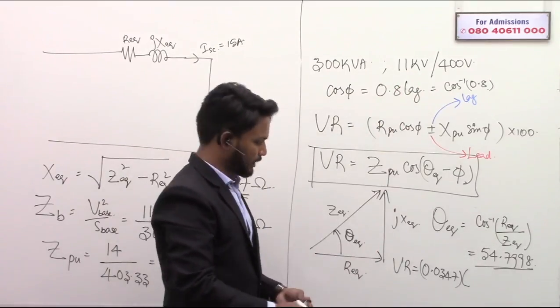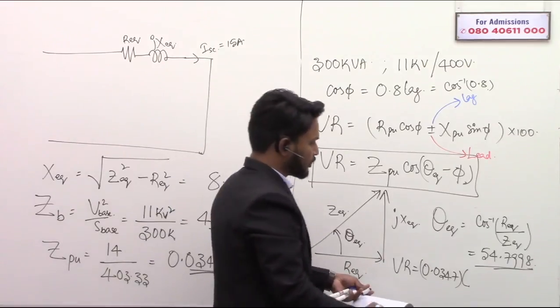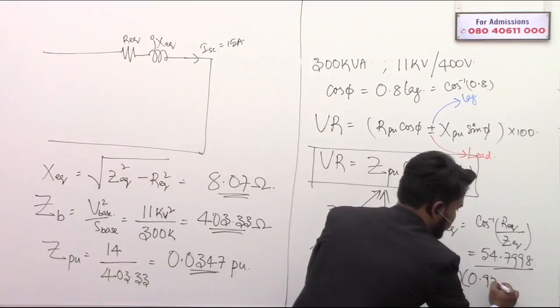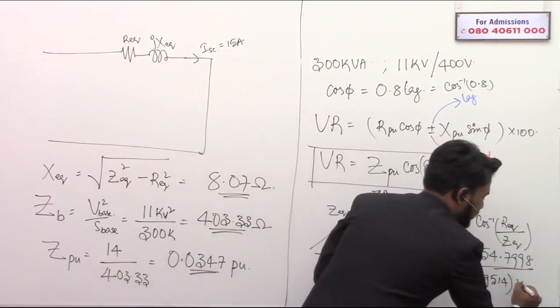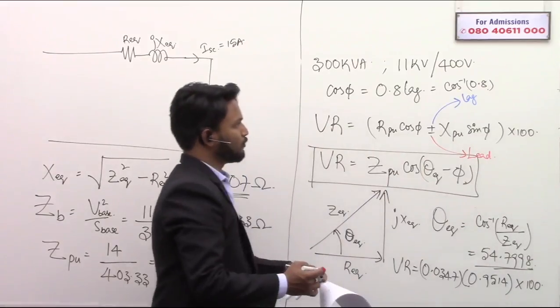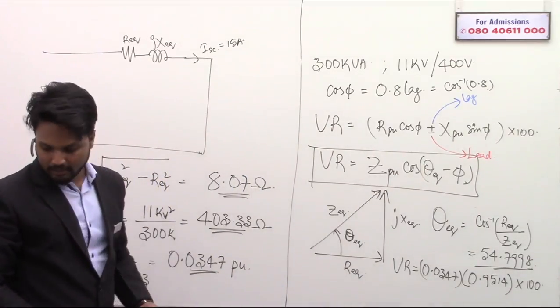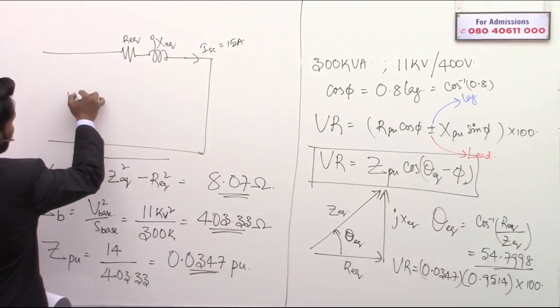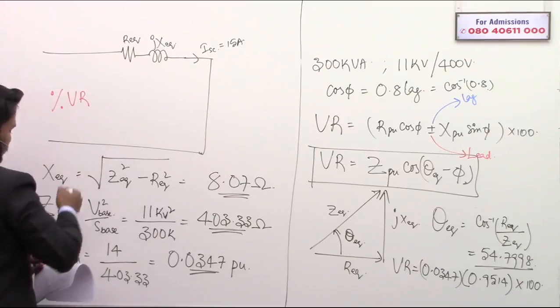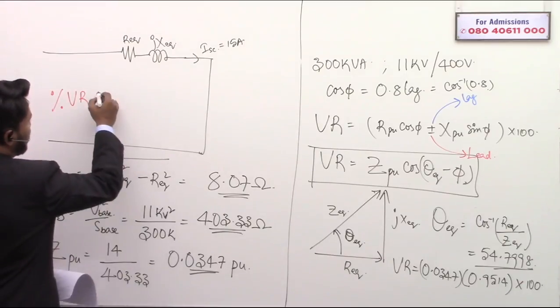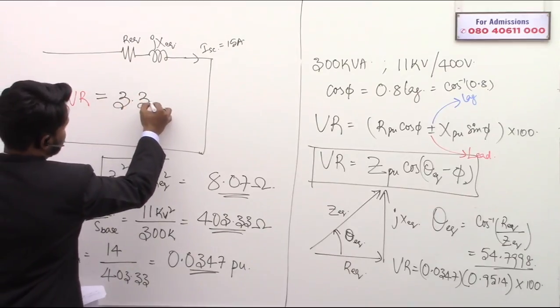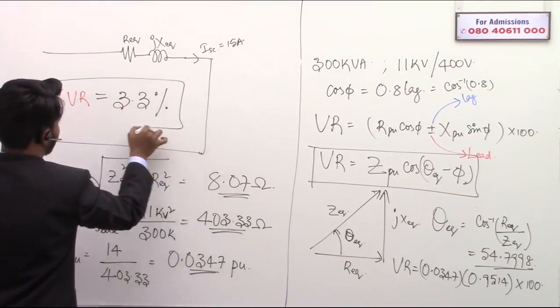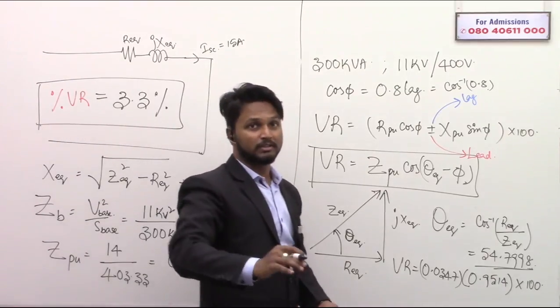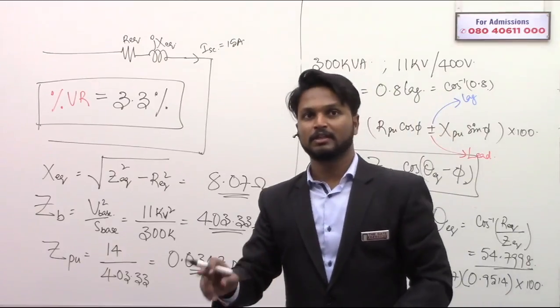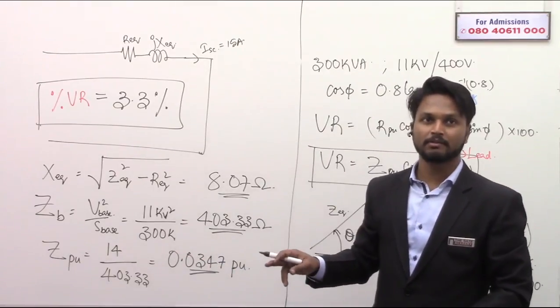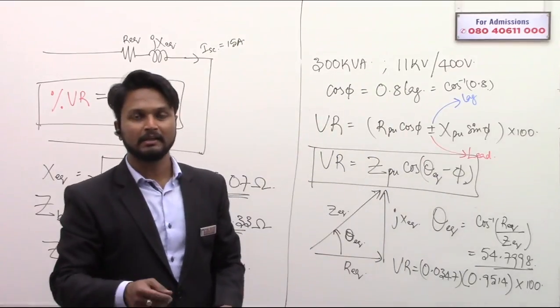So cos inverse of 0.8, this value is going to be 0.9514. Both these things multiplied by 100 will give you percentage voltage regulation. There is no space here, I'll write it in this column. Percentage voltage regulation VR is equal to 3.3%. If you simplify this, you'll get approximately 3.3%. So this is the voltage regulation at full load, 0.8 lagging power factor.